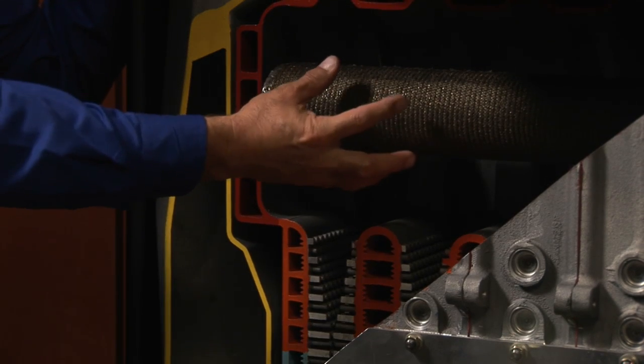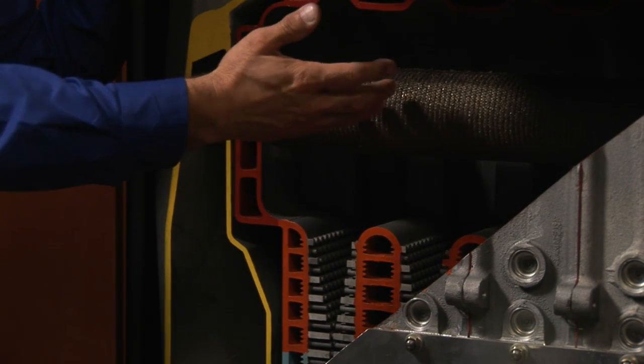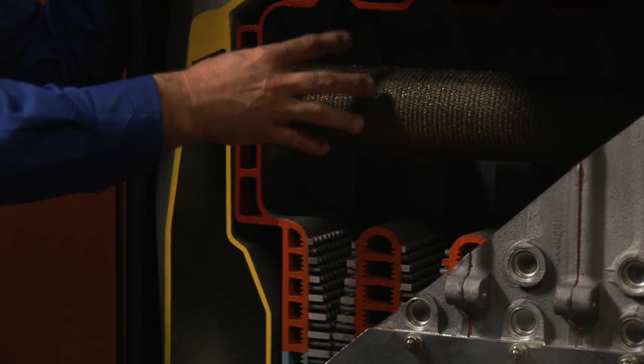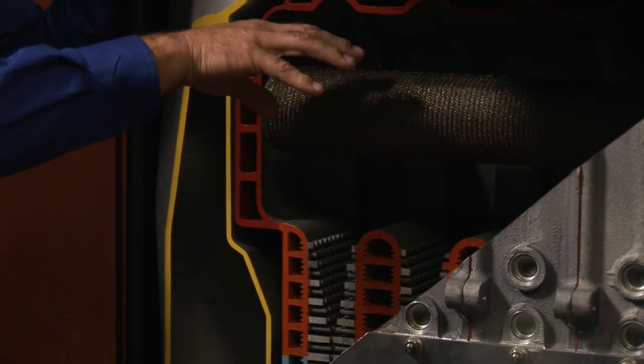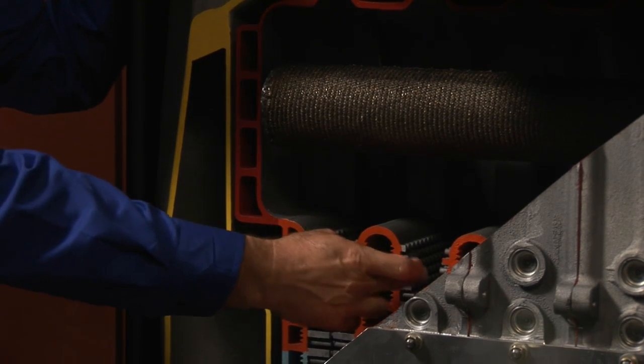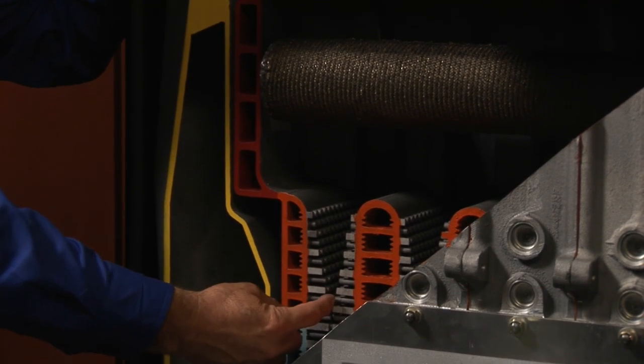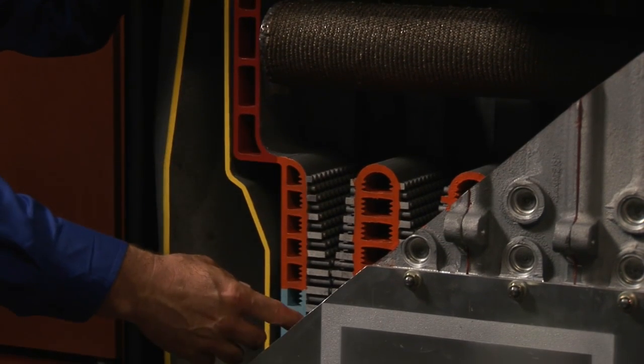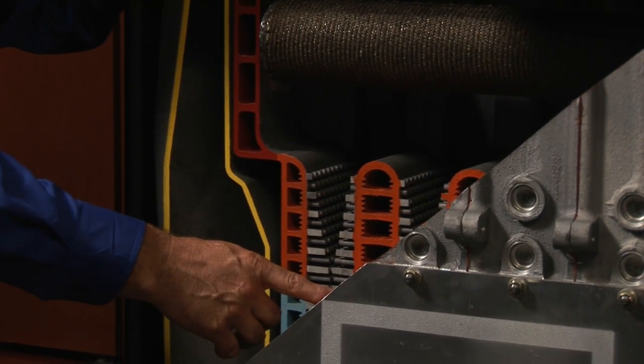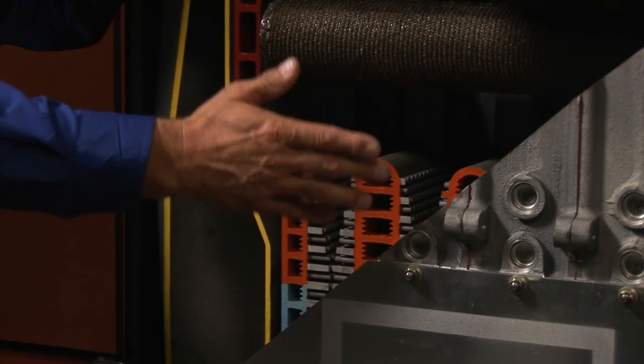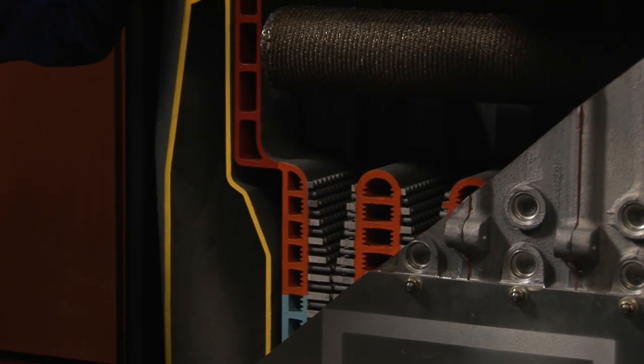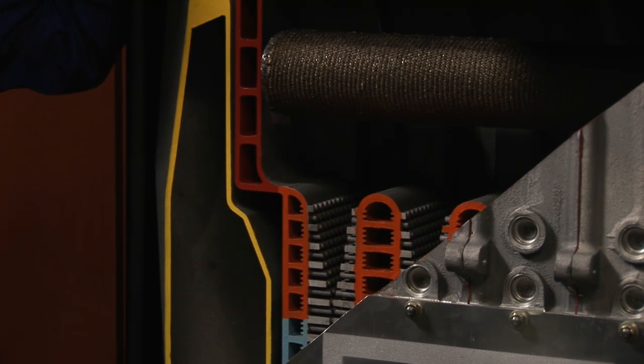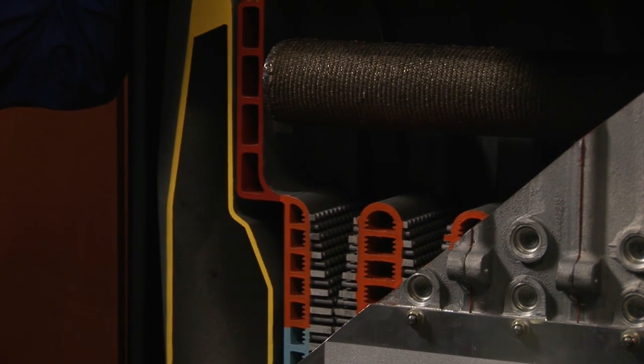So as we send the gas down through the burner, we ignite, we fire onto the burner, and then we force the flue gases down between this pin area, and the heat is extracted through the pins, transferred into the waterways, and we heat the water, and then it comes up to the top of the boiler and exits out through the top of the boiler and heads off to the heating system.